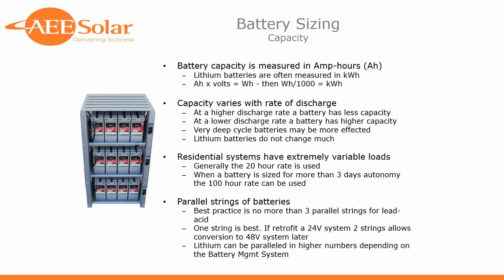And when you're looking at designing a system, particularly with lead type batteries, any of them, best practice is not to have more than 3 parallel strings in order to get that capacity. The battery has a certain capacity. You have to put them in series to get the voltage you need for the system, and then put them in parallel to get higher capacity. 1 string is ideal, just because the more parallel strings you have, the more chance there is for imbalance between the cells.